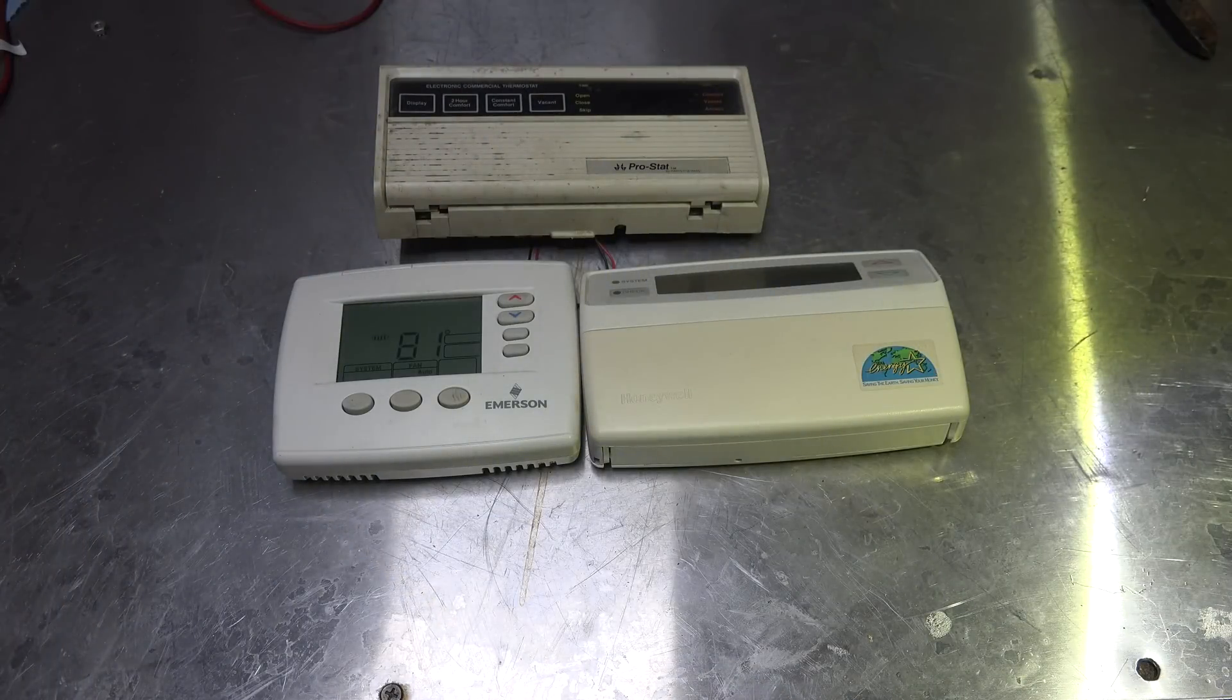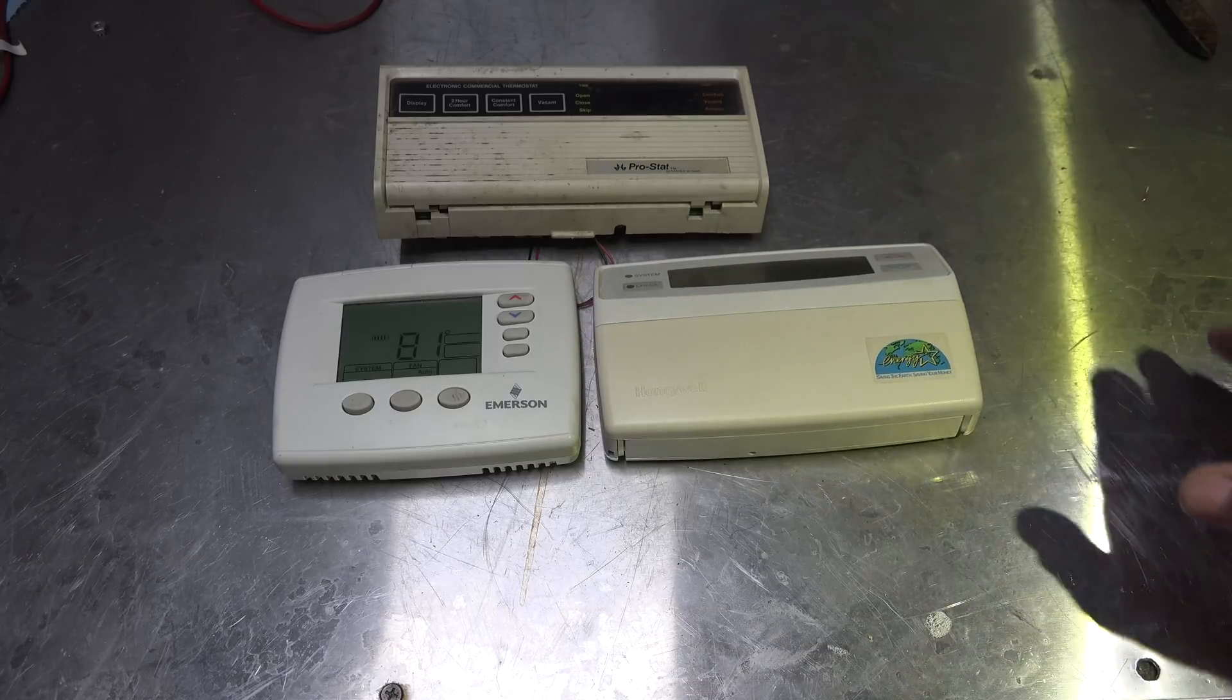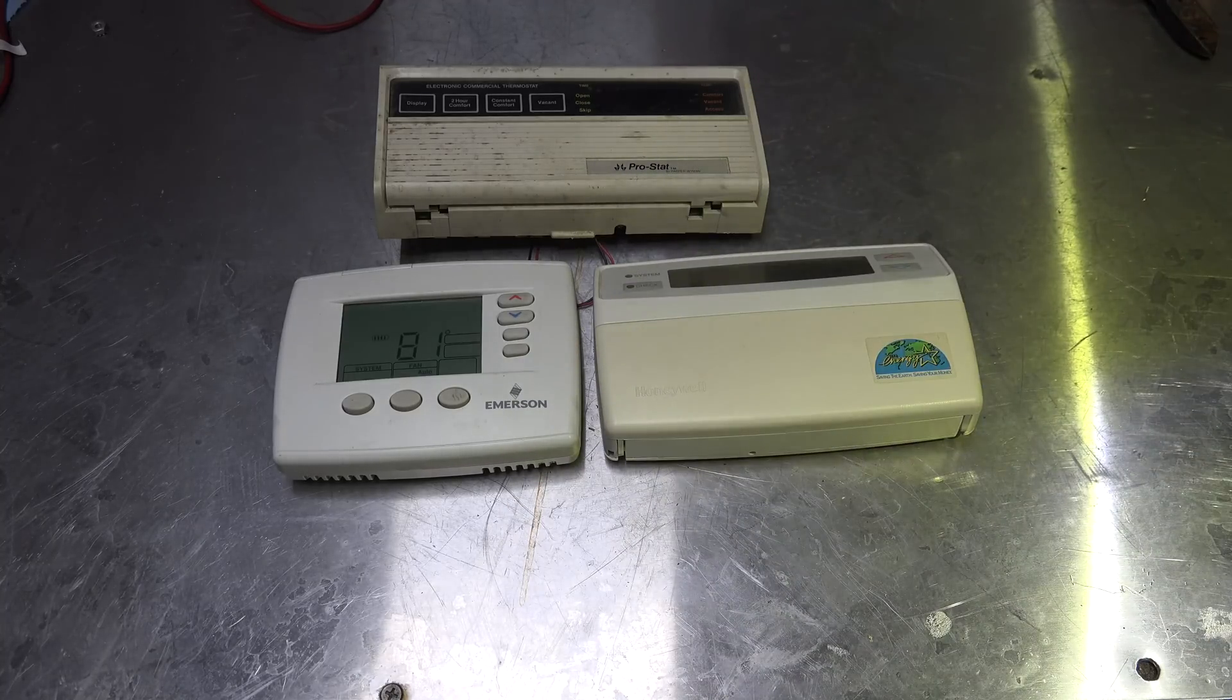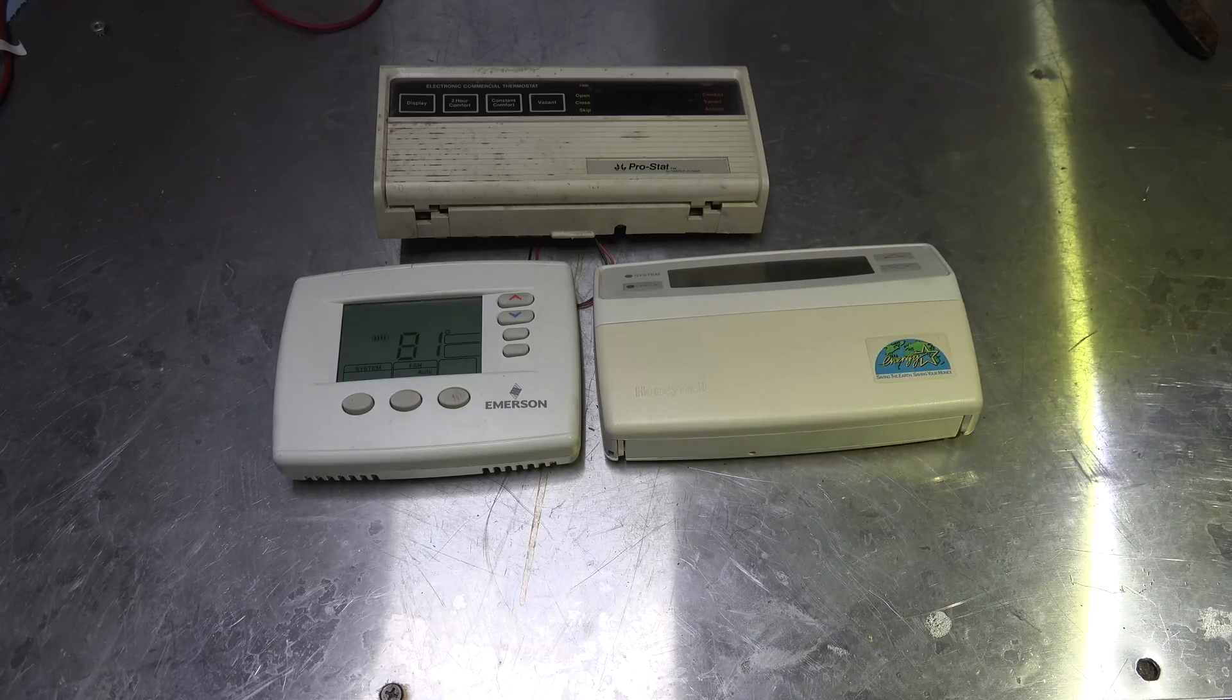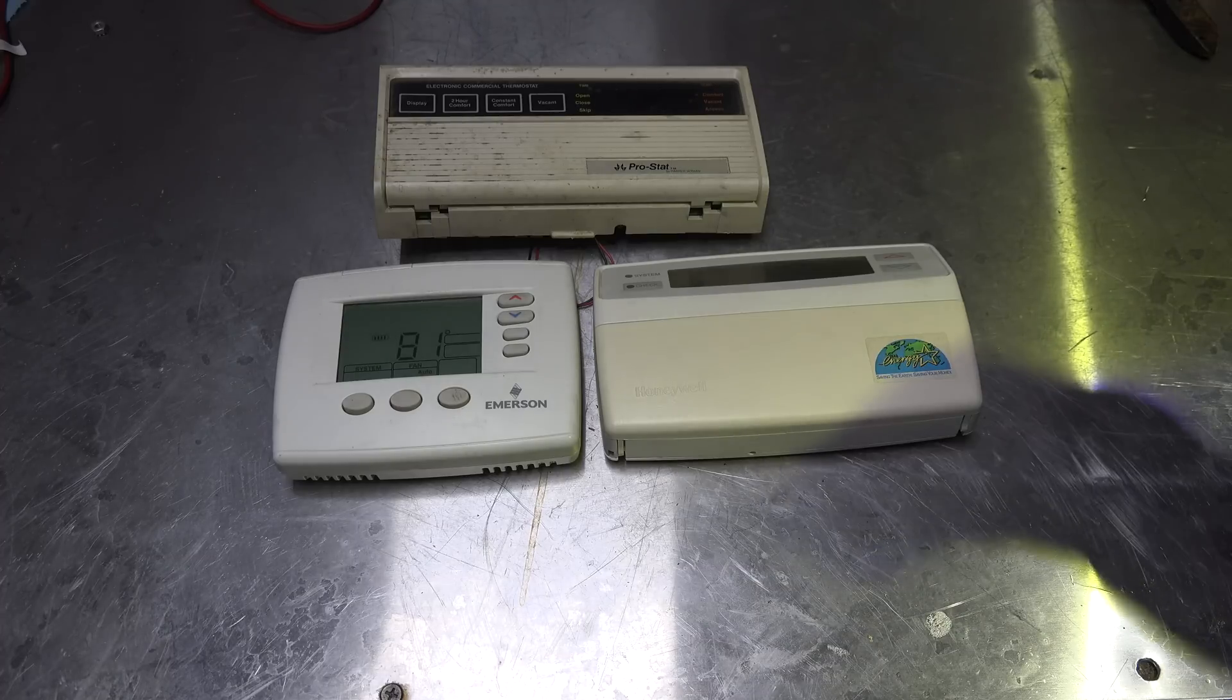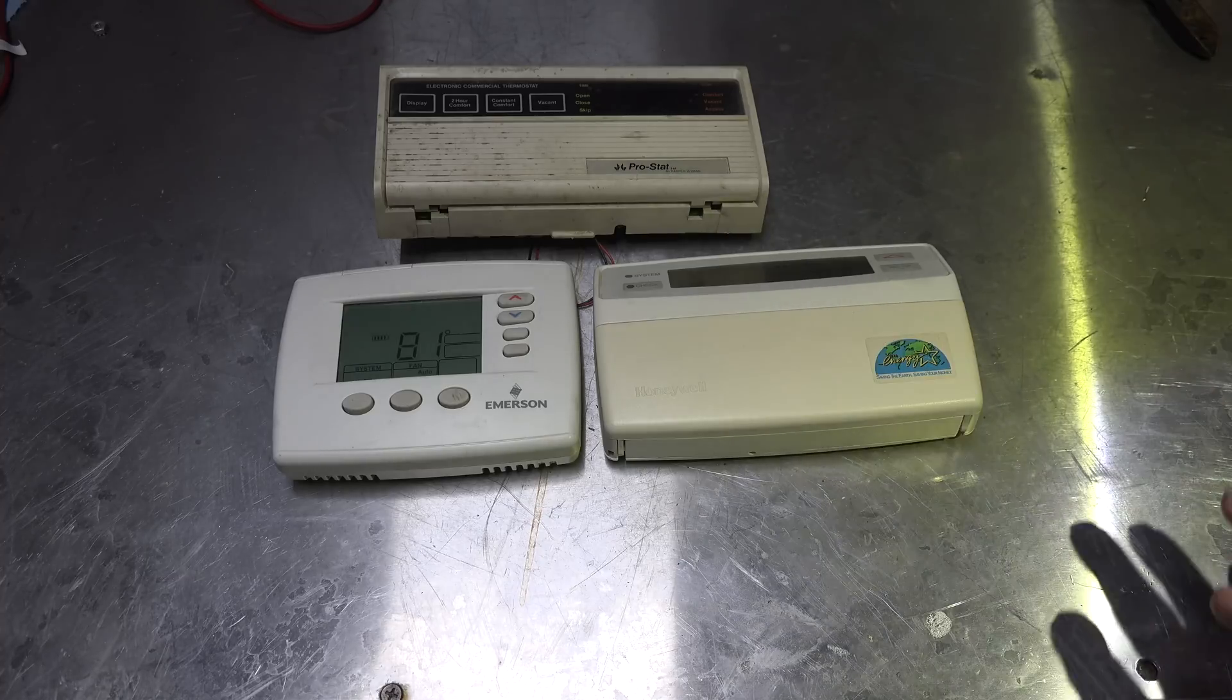What we're looking at on these thermostats is how they sense temperature. Where is the temperature sensor? What is it? How does it work? Well, these are all thermistor type thermostats. That means they use a variable resistor, which means as the temperature goes up and temperature goes down, the resistor changes its resistance. That's how these things work.